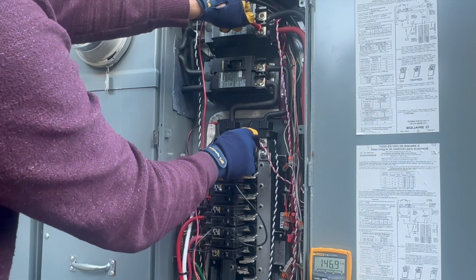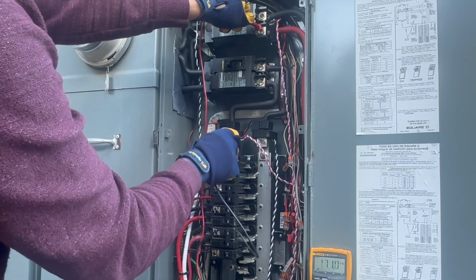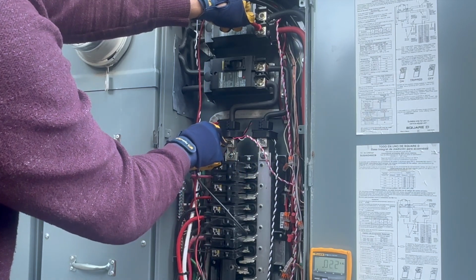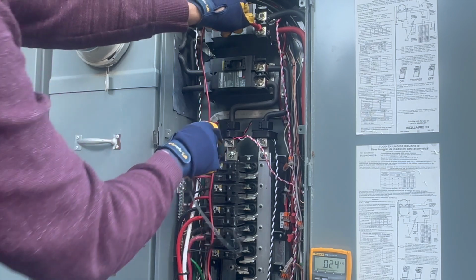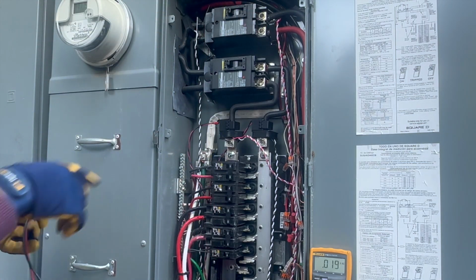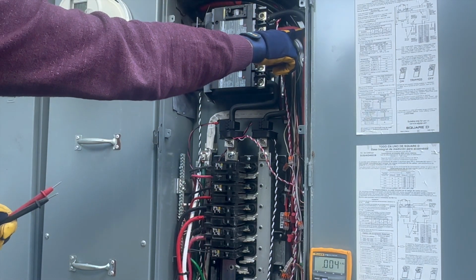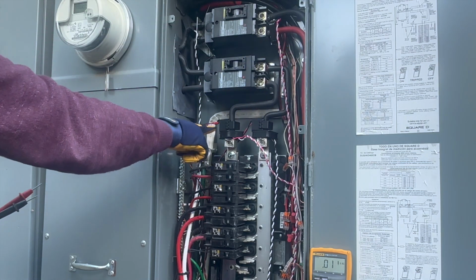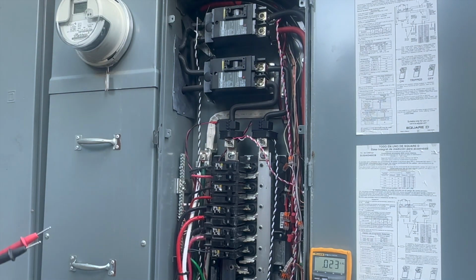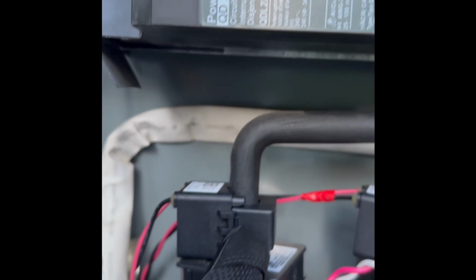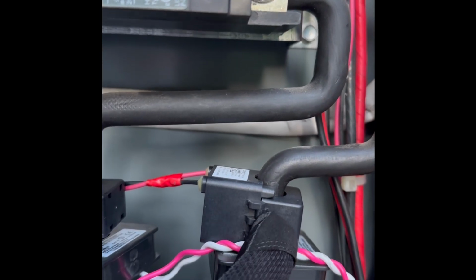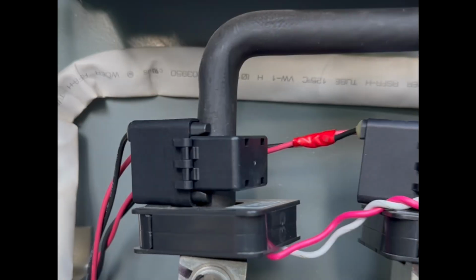Yeah, this panel has been wired such that the red phase on the top 200 amp breaker corresponds to the left-hand side of this bottom bus bar, which is odd. Again, I expected the left side to be the black phase, and it looks like the Tesla installers did too. So that's the problem. And again, why flipping these CTs kind of fixed things, but the right fix was to swap the CT1 and CT2 to the other phase.